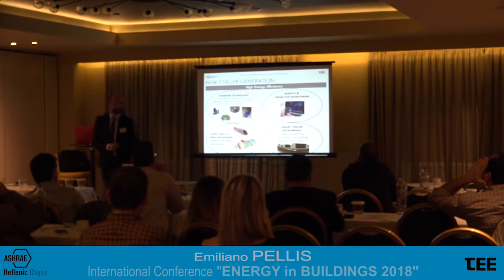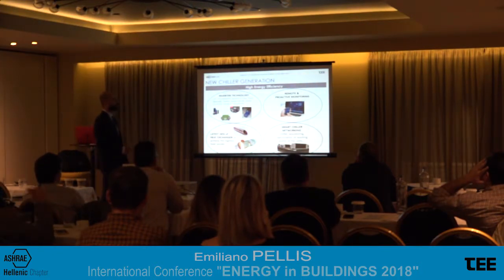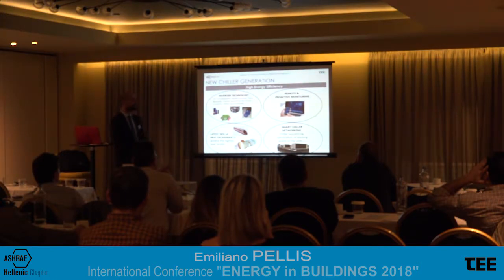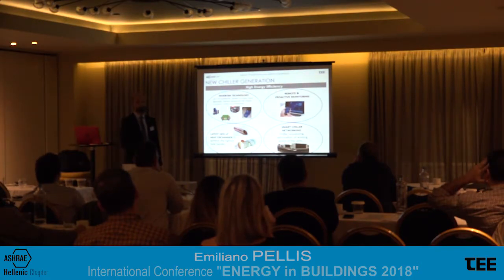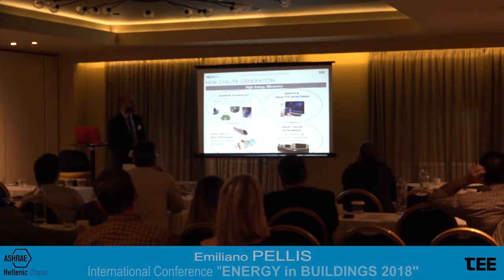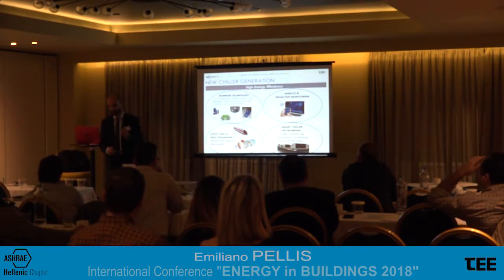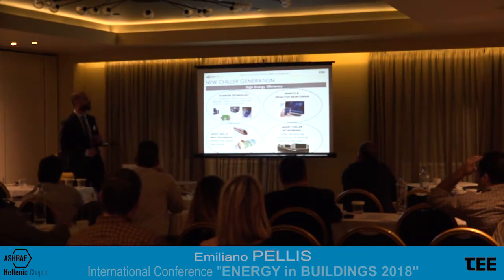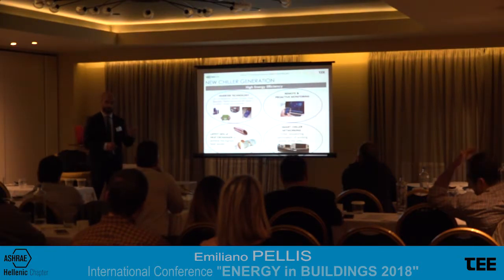I have tried to identify four key points to achieve high energy efficiency on our chiller. The first is inverter technology, applied not only on the compressor, but also on the water pumps and on the fans. The second point is the use of the latest generation of heat exchangers, for example by using high-performing enhanced copper tubes in the heat exchanger, the shell and tube type. Third point, remote and proactive monitoring. So we need to monitor the chillers remotely and introduce some corrective action in case of deviation.